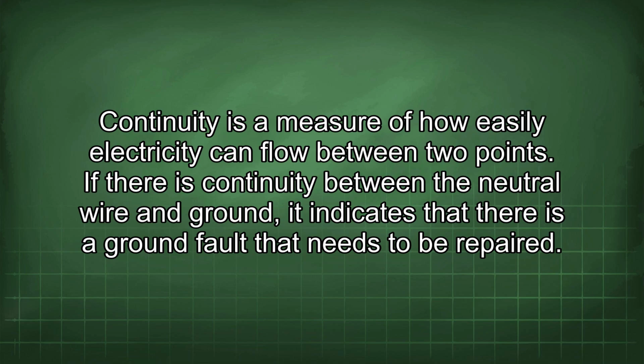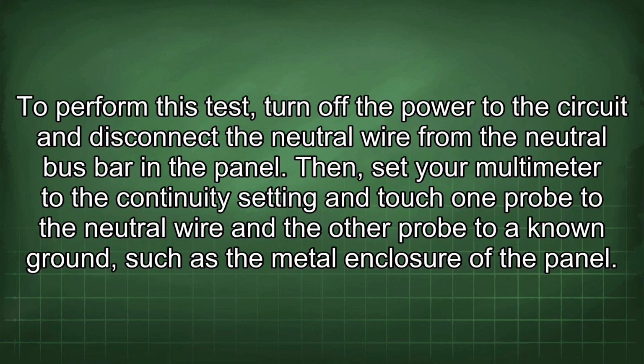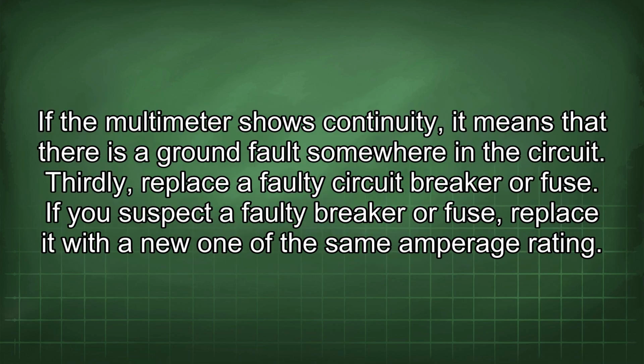to be repaired. To perform this test, turn off the power to the circuit and disconnect the neutral wire from the neutral bus bar in the panel. Then, set your multimeter to the continuity setting and touch one probe to the neutral wire and the other probe to a known ground, such as the metal enclosure of the panel. If the multimeter shows continuity, it means that there's a ground fault somewhere in the circuit.